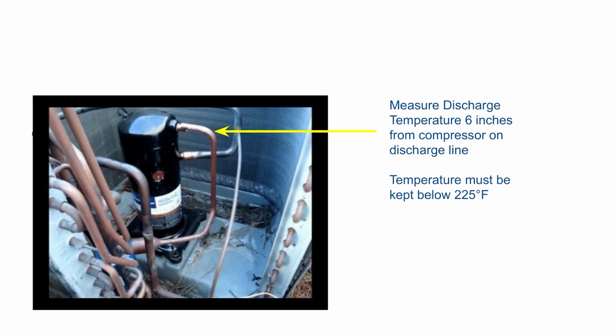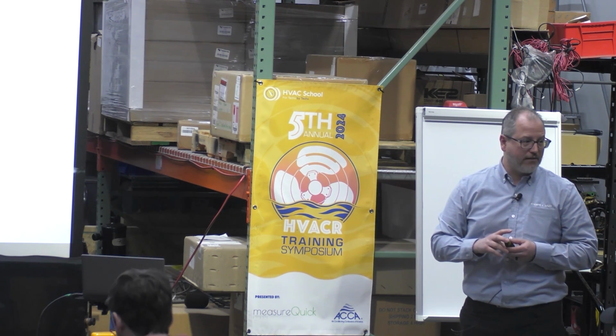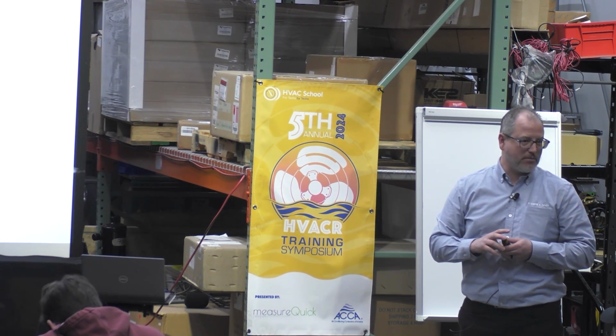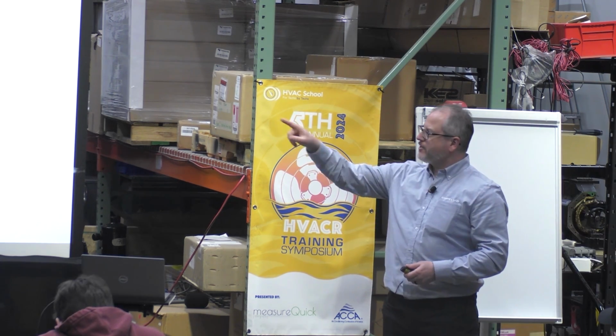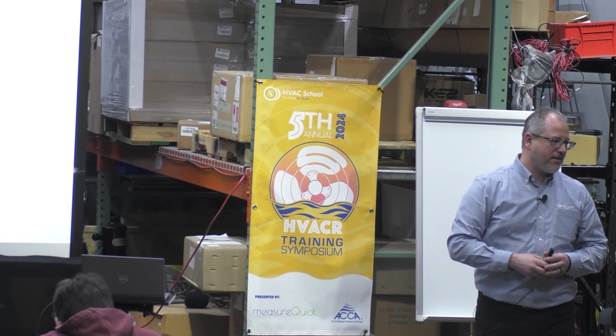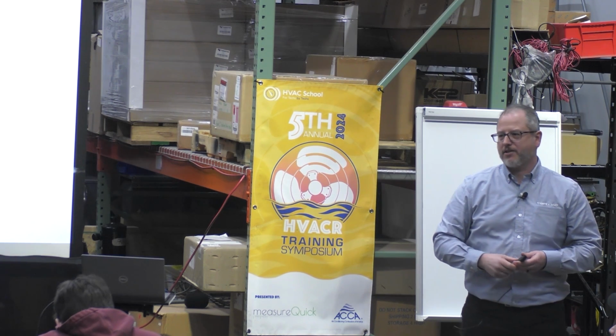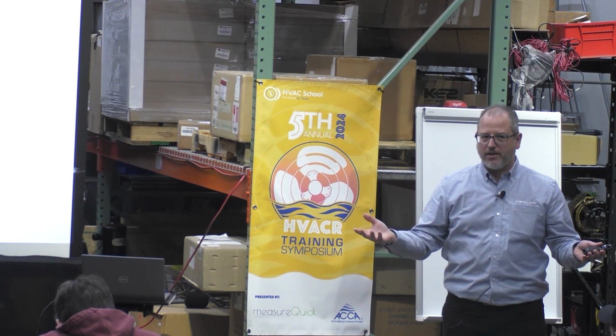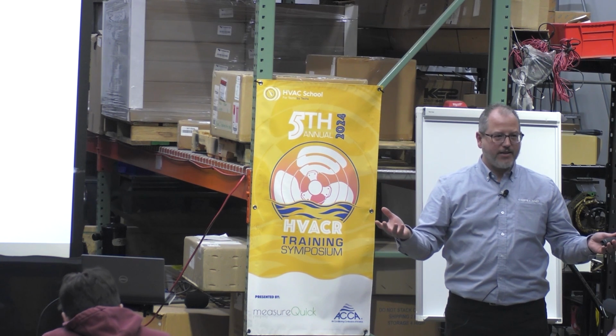We always want to check our temperature 6 inches away from our compressor, and it should be no higher than 225 degrees. Okay? So 225 to stay alive. Just remember that, 225 to stay alive. If it's 225 there, it's 50 to 75 degrees warmer inside of our compressor. And what temperature does the oil start breaking down at? Yeah, it kind of sounds familiar, right?